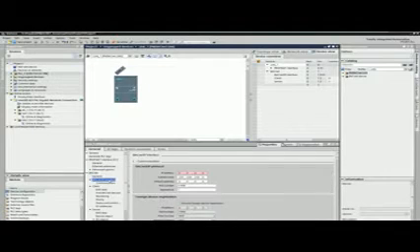The properties for BACnet can be configured under the menu item BACnet. At first, an IP address must be assigned. To do this, call the BACnet IP interface setting and configure an IP address. This address must be unique in the network.